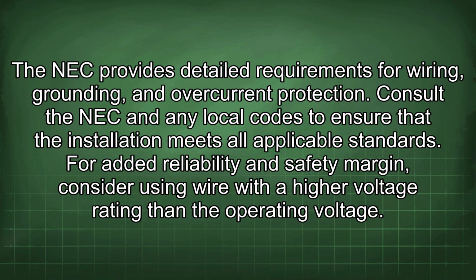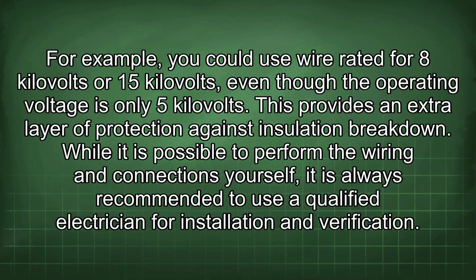For added reliability and safety margin, consider using wire with a higher voltage rating than the operating voltage. For example, you could use wire rated for 8 kilovolts or 15 kilovolts, even though the operating voltage is only 5 kilovolts. This provides an extra layer of protection against insulation breakdown.